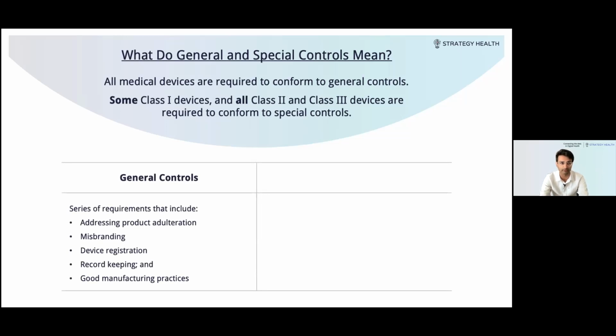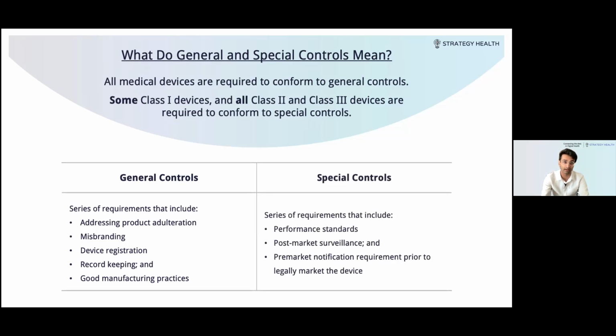What are these controls? What do I mean by that? In essence, general controls are a set of requirements that guide product developers on how to address adulteration of products, how to address branding and misbranding, how to register your device, internal record keeping, and following good manufacturing practices. These things, even though they're required by the FDA, should probably be part and parcel of product development, full stop. I think it's just general good practice to have all of these things in place, even if your product ends up not technically being a medical device. Special controls are a level above: increased performance standards and an assessment of performance standards, having post-market surveillance abilities and plans in place, and then doing the pre-market, so letting the FDA know that you plan, hopefully, to start marketing your device.